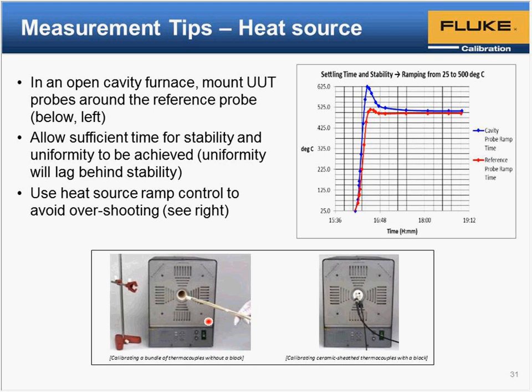Part of it depends on what you're willing to put up with in your own calibrations. But for example, if I was doing this test at room temperature and the thermocouple jumped by a half degree at some inhomogeneous section of wire, I would probably just reject it, because a new, properly working base metal thermocouple should not have half a degree inhomogeneity in this test. So we're trying to develop some more advice on that to help you make sense of inhomogeneity.